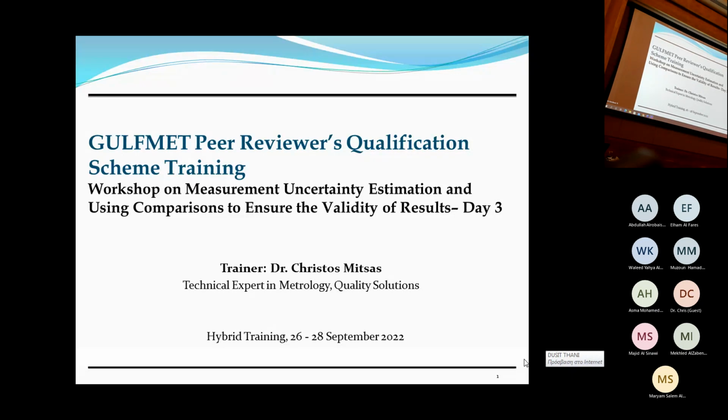Yes. If you wanted to put the error for the resolution that way, then the standard deviation would be half of the digit divided by the square root of 3. So you would have to calculate it and then enter it into the software.